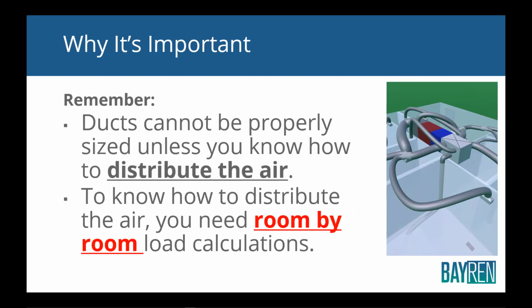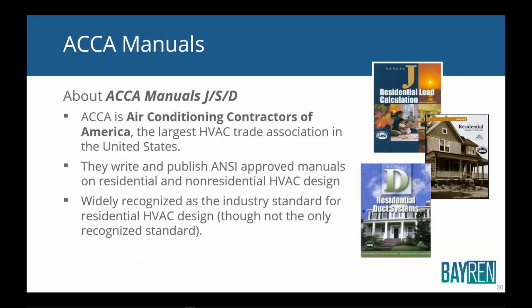Ducts cannot be properly sized unless you know how to distribute the air. And the only way to know that is to do room by room load calcs. I've seen giant rooms on the north side of the house with a little bit of glass need half as much air as a much smaller room on the west side of the house with a big sliding glass door. So airflow is not proportional to square footage. Glass area, glass direction, and things like that have a much bigger impact. In fact, 1 square foot of glass is 25 times more important than 1 square foot of wall in a house. So glass is very important. And again, the only way to do that is to do a load calc.